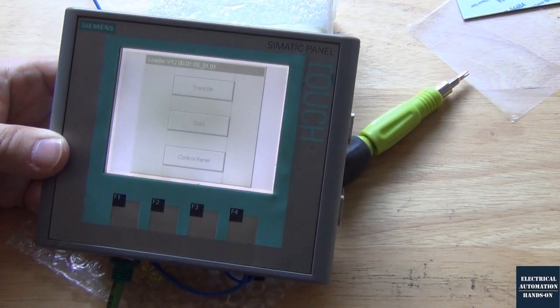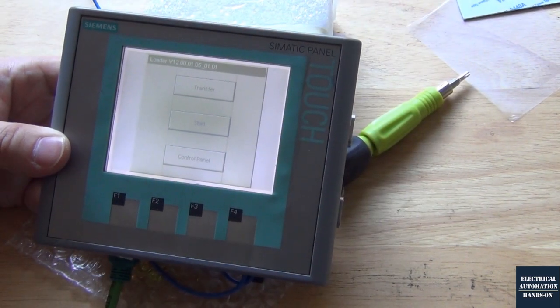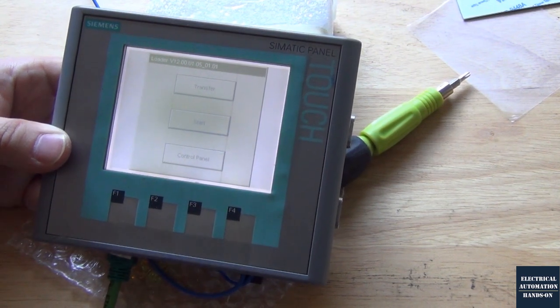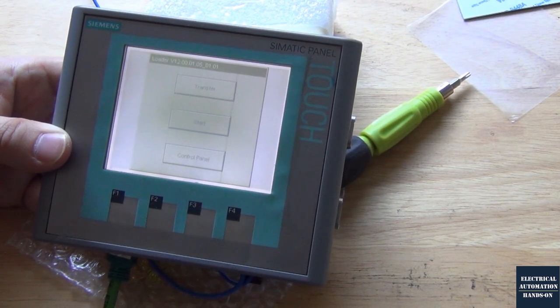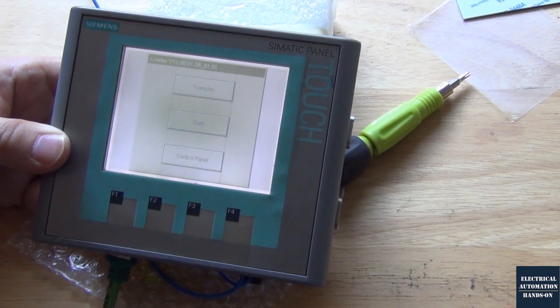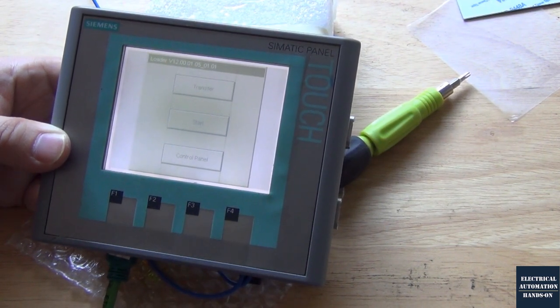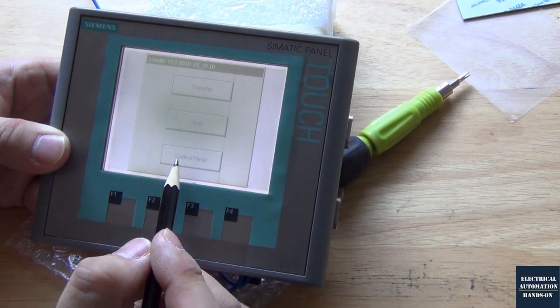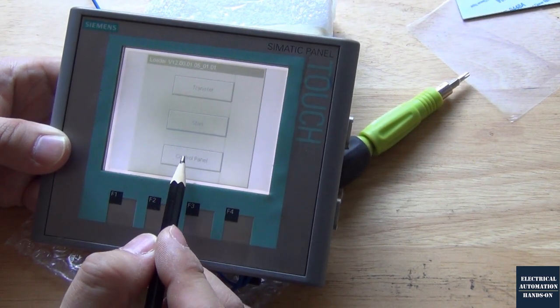After we replace this new touch screen, we better do a calibration to calibrate our touching position. We better recalibrate the touching function. So to enter the recalibrate function, reboot the HMI. And while it's rebooting, we can jump to the control panel.